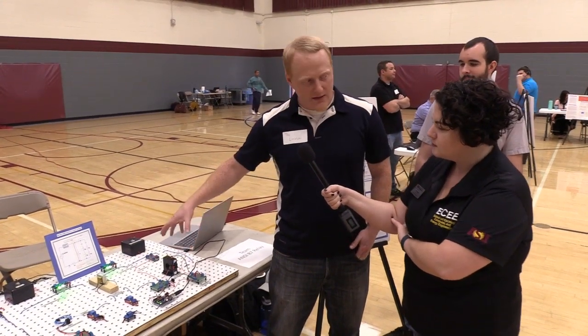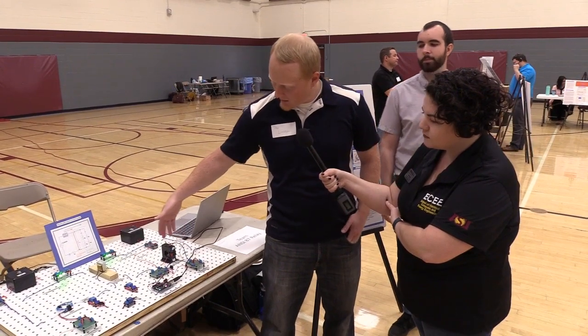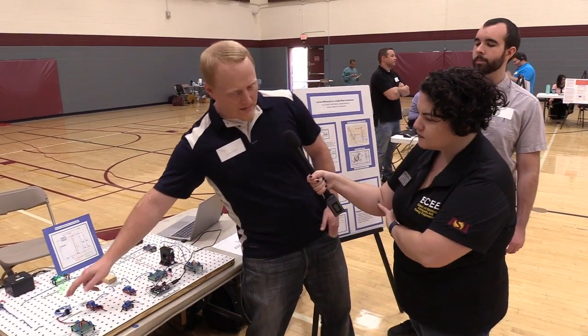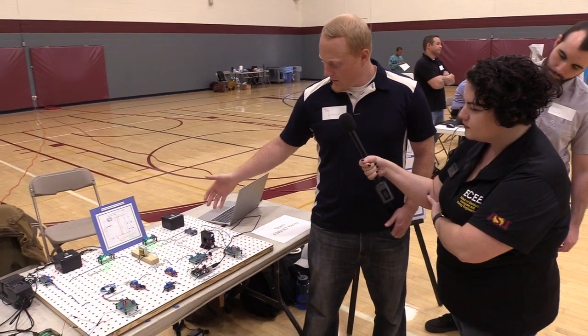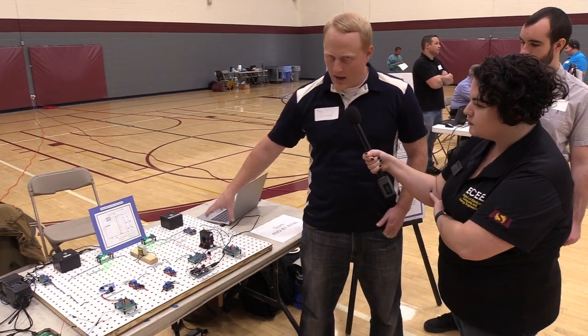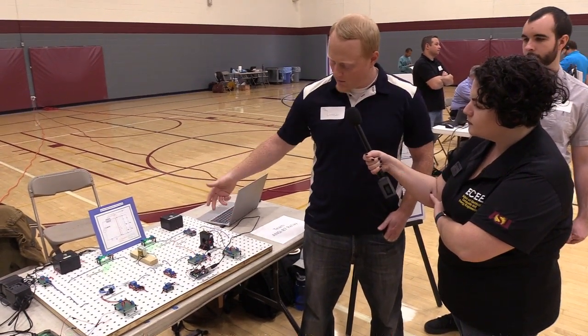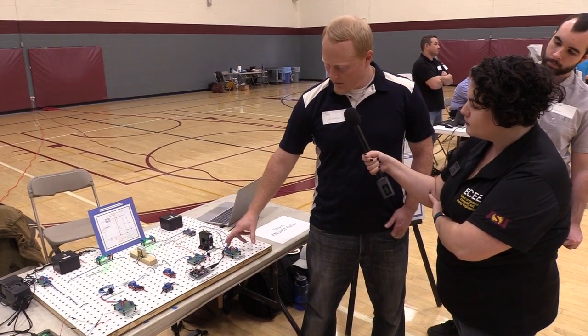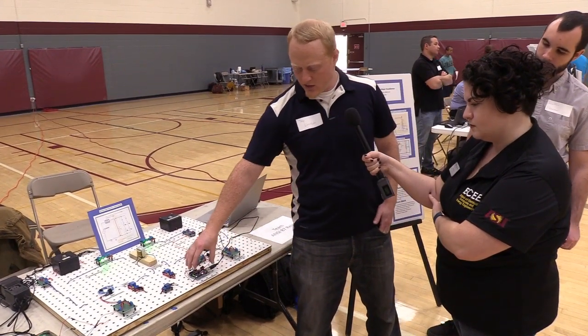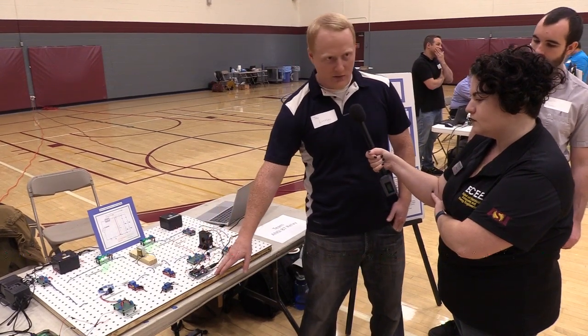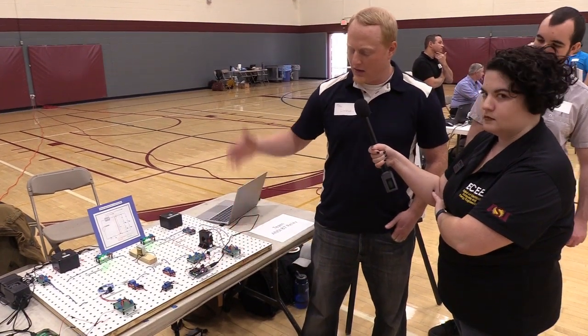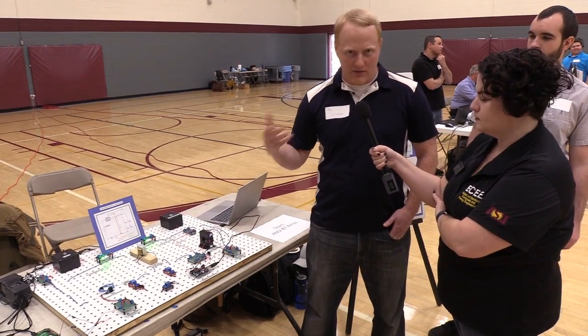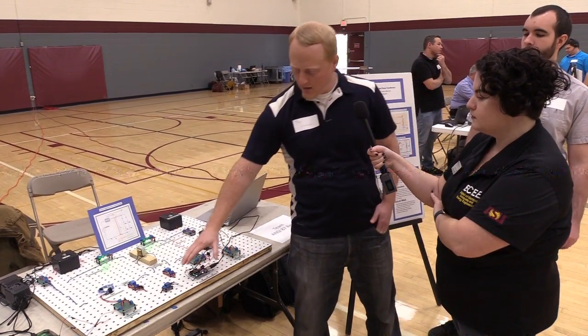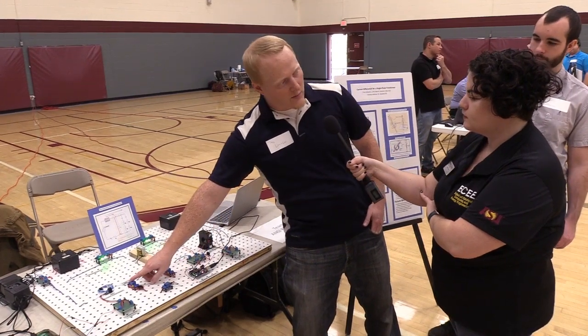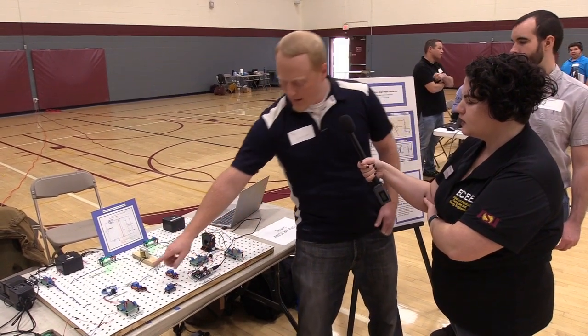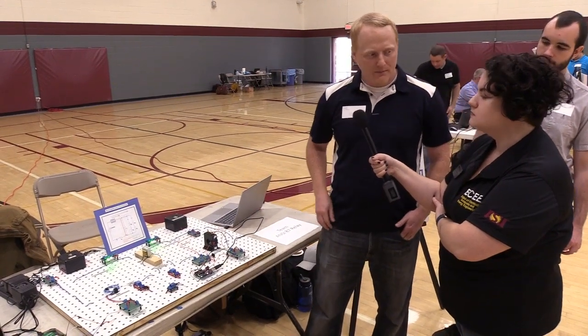The current transformer is actually sampling the amount of current flowing through the power line. There's one here, and there's a smaller one on this side. Those two are keeping track of what's happening on the transmission line on either side of the transformer. It feeds that signal down to these boards here, and that gets fed to the actual current differential itself. This is the device that makes the decision on whether or not there's a fault, and if it sees a fault, it sends a signal out via these relays here, and this is our actual circuit breaker. If this sees there's a problem, it opens up and isolates everything.